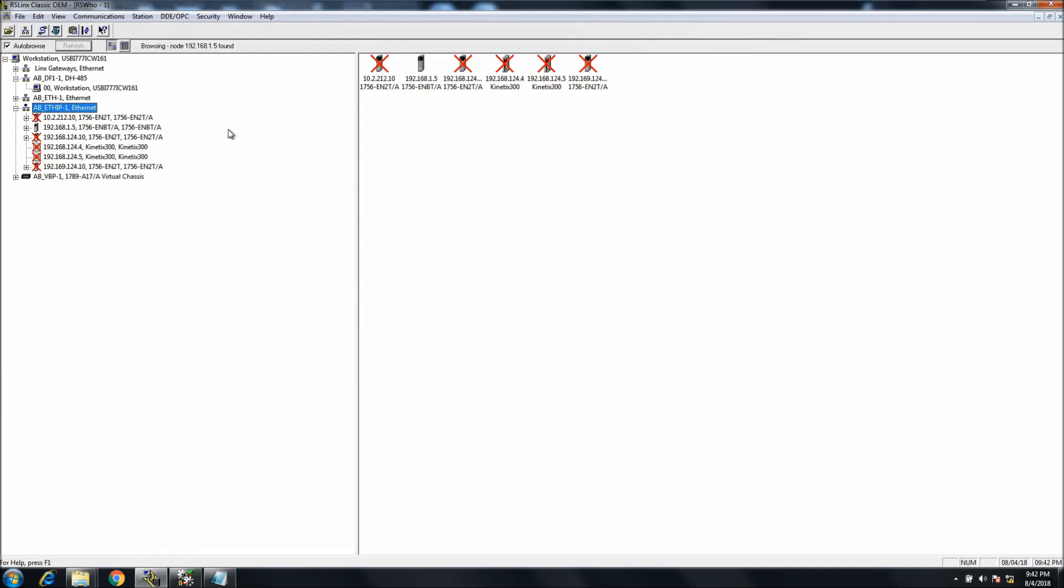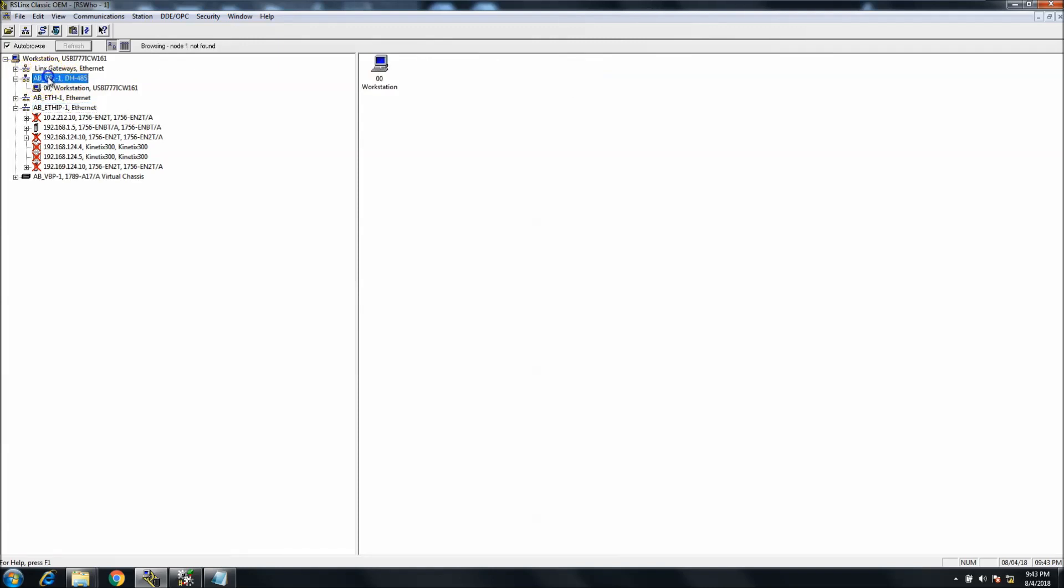Well, you can get online with it. There is a serial port on top of the SERCOS itself, or the top of the Kinetix 6000 drive itself. But you have to have the 1203 USB or a compatible module to be able to talk to that. At that point it is a serial connection, therefore you're using the AB DF1 driver. The DF1 driver is able to be used with that 1203 USB.